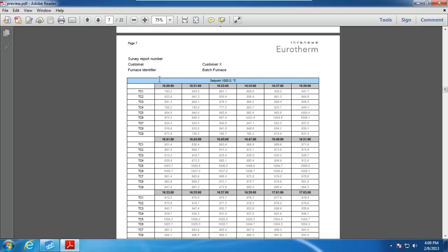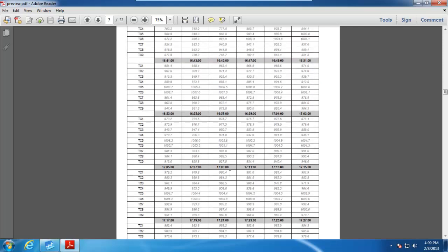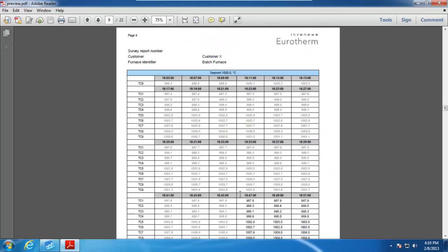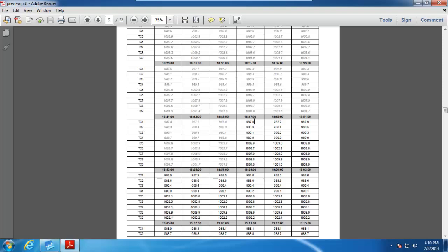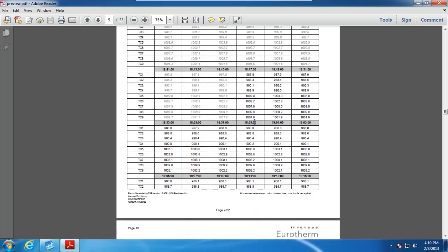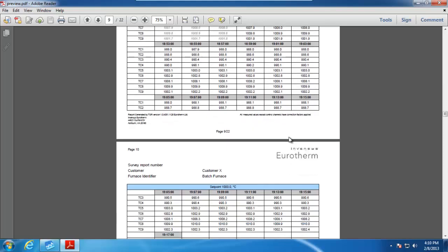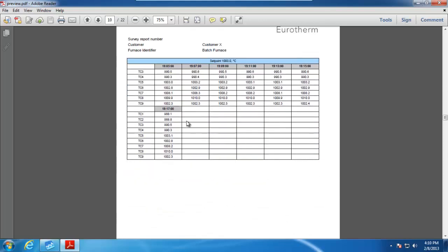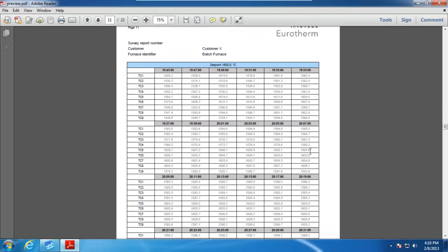So you notice that it starts at about 4:30 in the afternoon, but it wasn't until roughly 6:47 that we started our stable measurement period. So for every 2 minutes during 6:47 on, we're going to have a reading of what we had during that 30 minutes. Finishing up at 7:17, we have our 30 minutes of data. And we can go on to set point number 2.